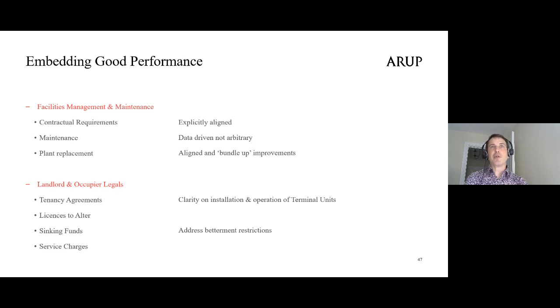Hand in hand with that, the default maintenance framework in the UK, SFG 20, uses planned preventative maintenance, which is fairly arbitrary: you check and replace equipment based on its type and age. You can move to more efficient maintenance by using performance data to target resources. So instead of checking all your fan coil units four times a year, you could check twice a year, but pay more attention to what the building is doing, focus on problem areas sooner, and potentially avoid a hot and cold call. Colleagues like Rick Davis are actively working to write new FM contracts implementing condition-based maintenance, explicitly written in to improve performance and use data to target maintenance resources more effectively.